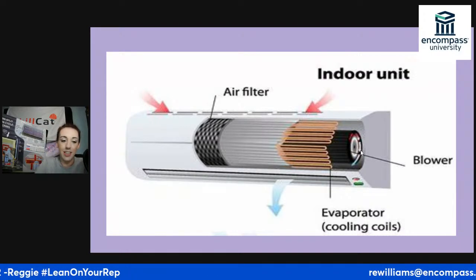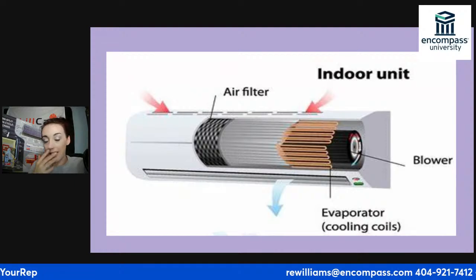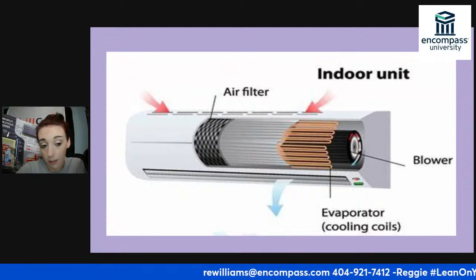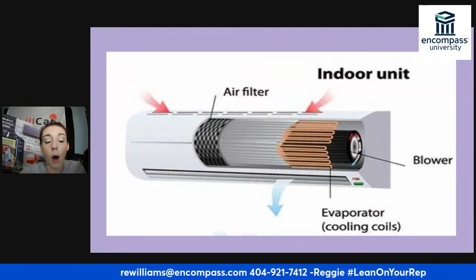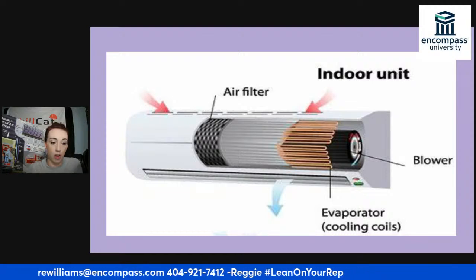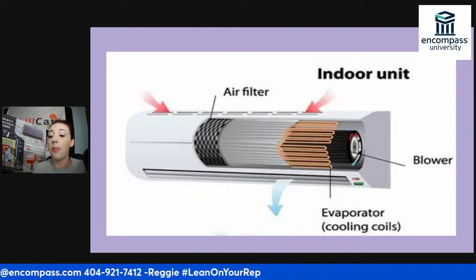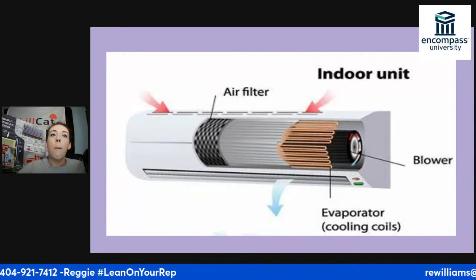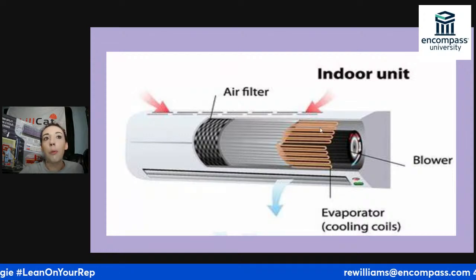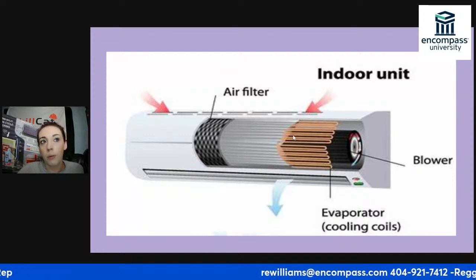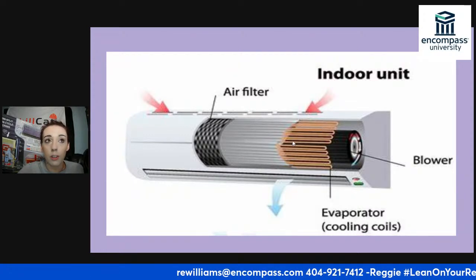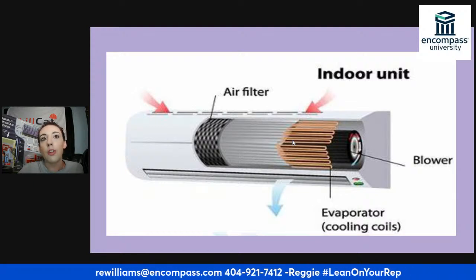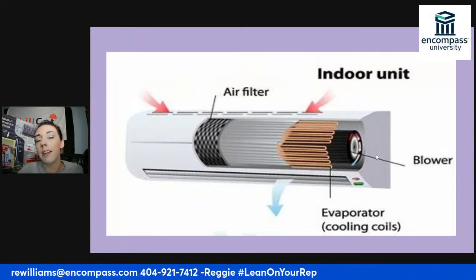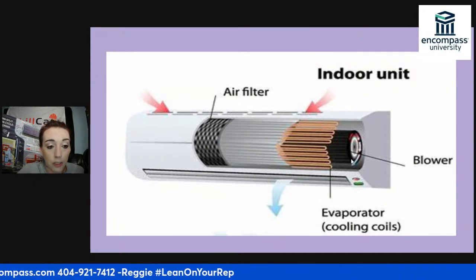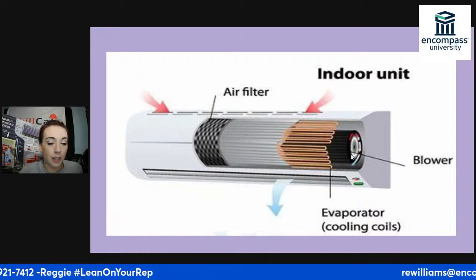What I see a lot of the time, especially with maintenance technicians who don't understand a lot about HVAC, not that technician's fault at all, that comes with the job. We know a little bit about a lot of things and we do what we can. But what I find a lot is that they will check the air filters, they will check the coil, and the coil looks clean, appears clean on the outside. So they don't bother to look behind at the blower wheel, or they don't know that's what's blowing. They don't know it's a component of the indoor coil.